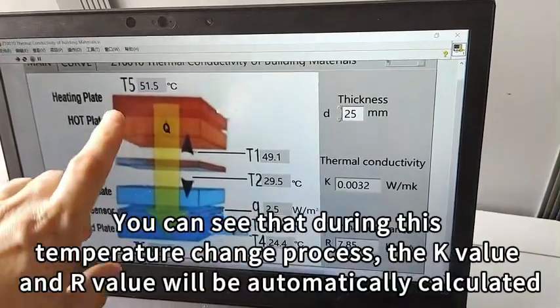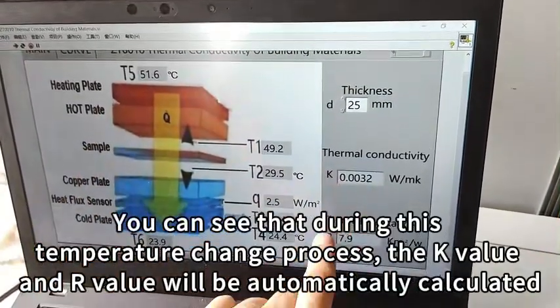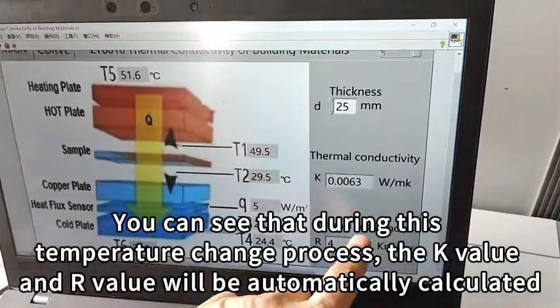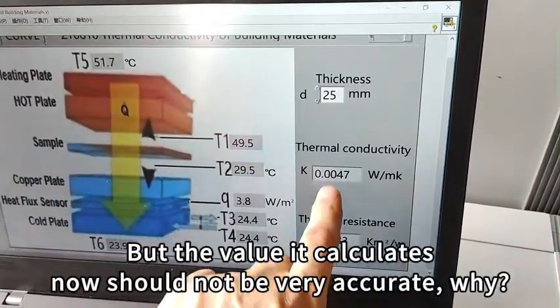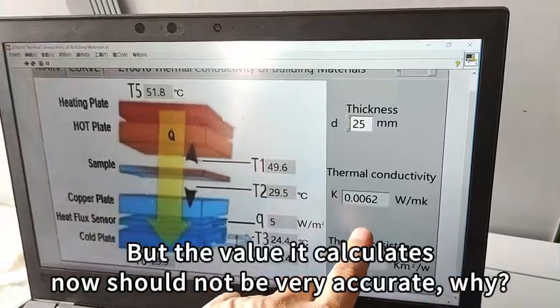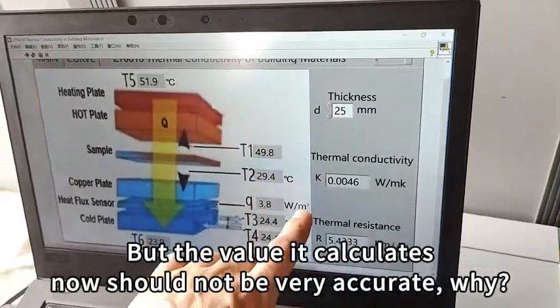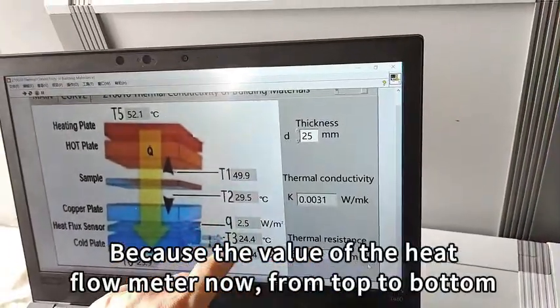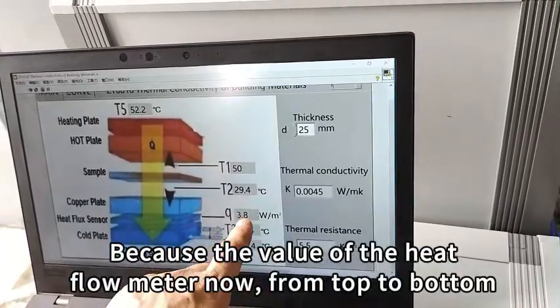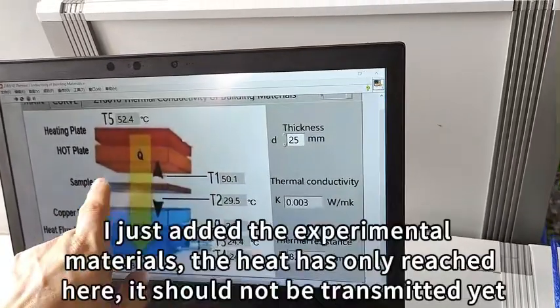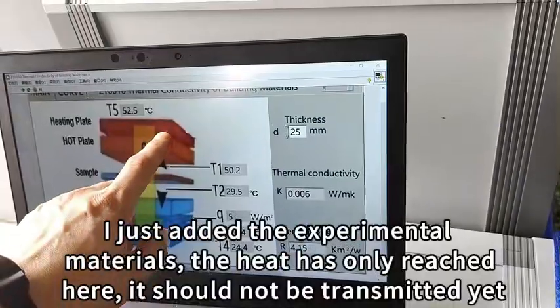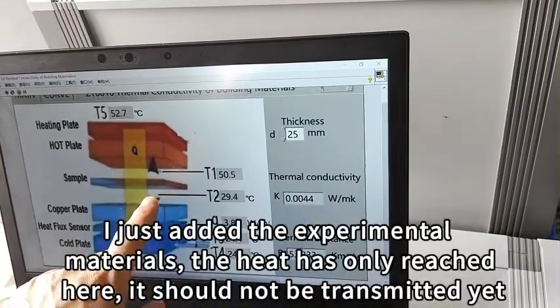You can see that during this temperature change process, the K value and R value will be automatically calculated. But the value it calculates now should not be very accurate. Why? Because of the value of the heat flow meter from top to bottom. I just added the experimental materials. The heat has only reached here. It should not be transmitted yet.